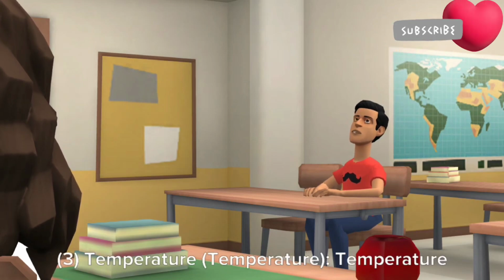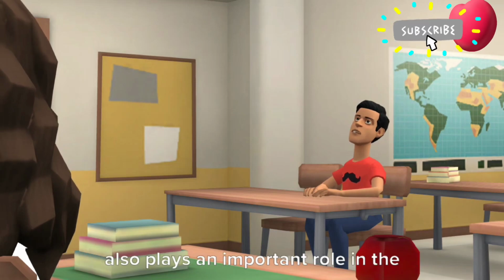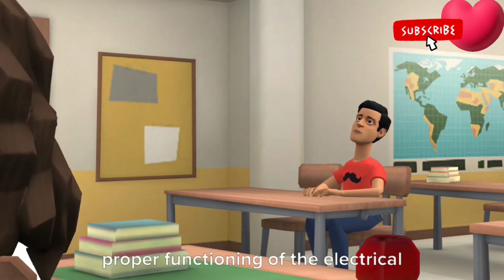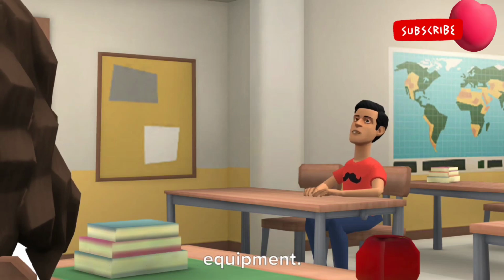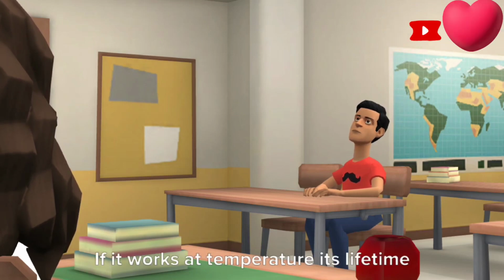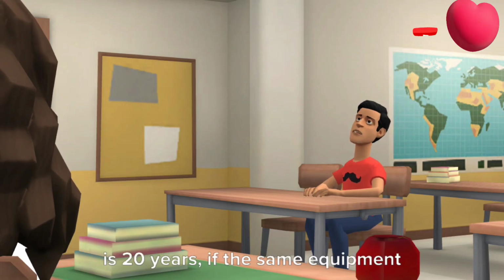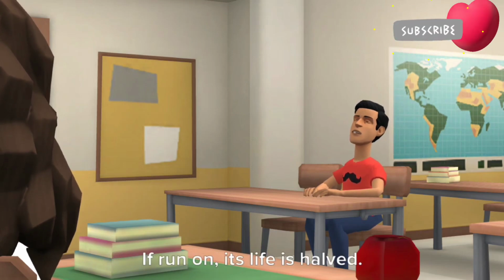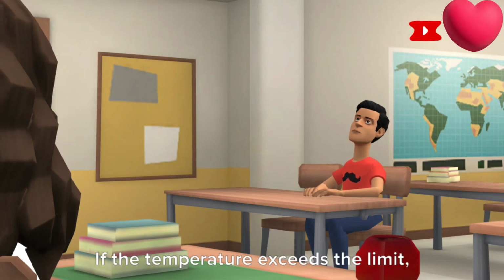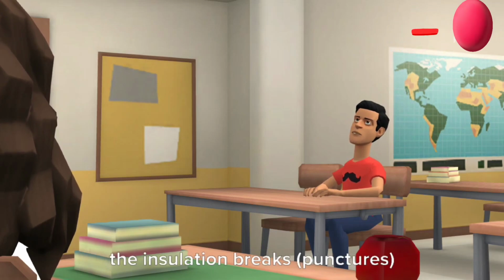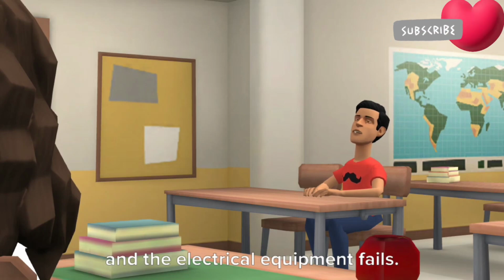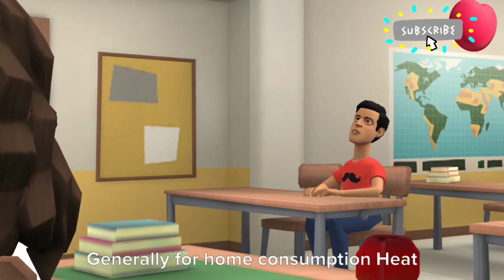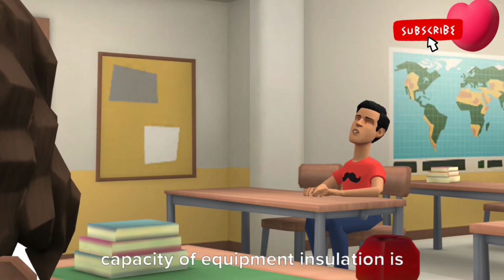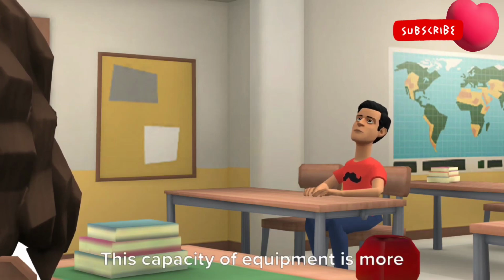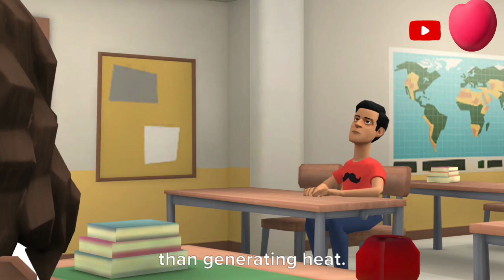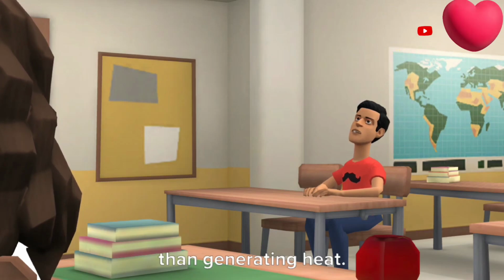3. Temperature also plays an important role in the proper functioning of the electrical equipment. For example, if an instrument works at 70 degrees Celsius, its lifetime is 20 years; if the same equipment is run at 80 degrees C, its life is halved. If the temperature exceeds the limit, the insulation breaks, punctures, and the electrical equipment fails. Generally for home consumption, the heat capacity of equipment insulation is 90 degrees Celsius. This capacity of equipment should be more than the heat it generates.